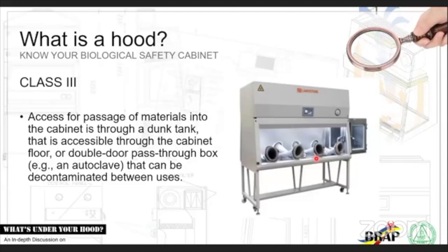Okay, so how it works is you have your pass box here. You place your material, close this one, insert your hands in the gloves, open this door, get your material out. Other systems have an attached autoclave at the end, and others have an incubator on the other end instead of an autoclave. So if you're processing your sample here, for example, a pure culture of your bacterium anthrax, you place it here, you manipulate it, you throw it inside your autoclave, which is attached to this portion, and that's it. So no contaminated material can ever escape this system. But do not use this for your routine, because this is a very, very, very expensive system to maintain.